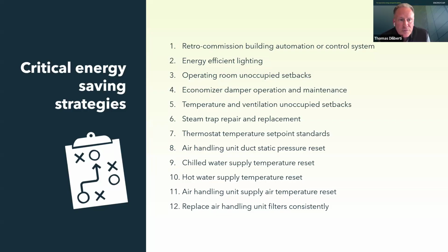So if you have one of those beautiful spring or fall days with low humidity and nice temperatures, economizers should open up and allow that air to flow in to flush out your facility and keep it comfortable and fresh. However, if it's raining outside, humid, or particularly cold, economizers should close and minimize the amount of air flowing into the facility.